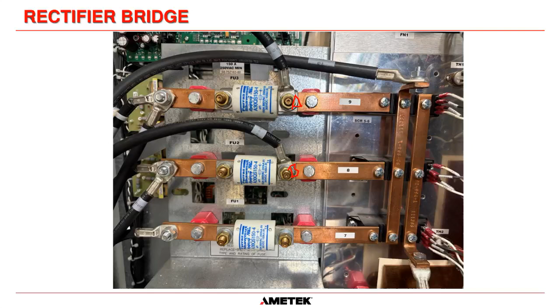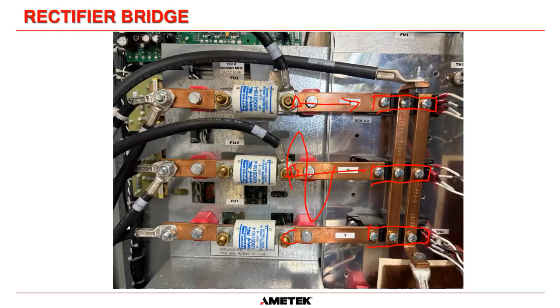And that is what it looks like inside one of our systems: A phase, B phase, C phase. So that is our AC into the bridge. Here is our SCR pack, one for each phase. It really is as simple as AC going in on the left through these three bus bars, and these two bus bars here are positive and negative. So it's AC in, DC out, and there's our gate leads going to the SCRs.